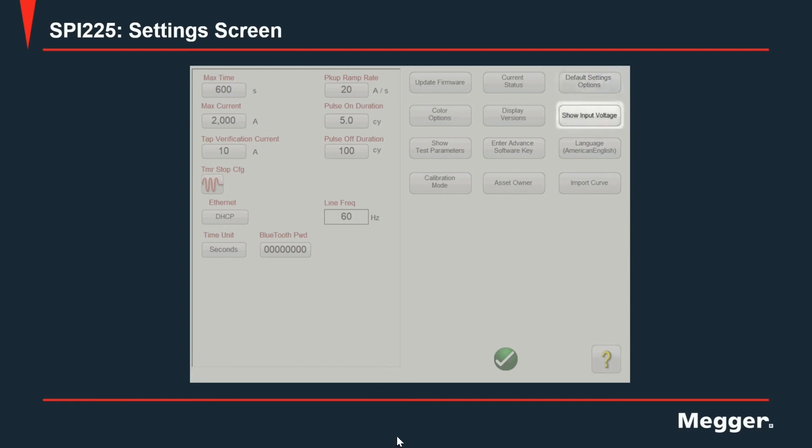Show input voltage is a function very important when troubleshooting the maximum current a unit can inject in a given configuration with a certain circuit breaker and a circuit connected to the output. When you have this setting enabled the input voltage will be shown in the test screen showing live values even during injections.